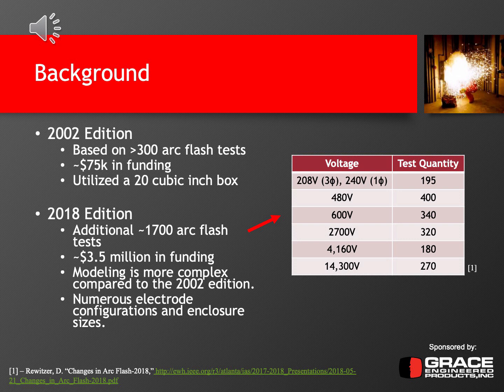The 2018 edition, however, ran an additional 1,700 arc flash tests. So the equations and the empirical data derived in 2018 is approximately 2,000 arc flash tests, so the 300 prior plus the 1,700. And the working group committee was able to secure about $3.5 million in funding to perform these tests, although the desired amount was about $6.5 million. So it fell relatively short of the requested amount, but still enough to perform all these tests.